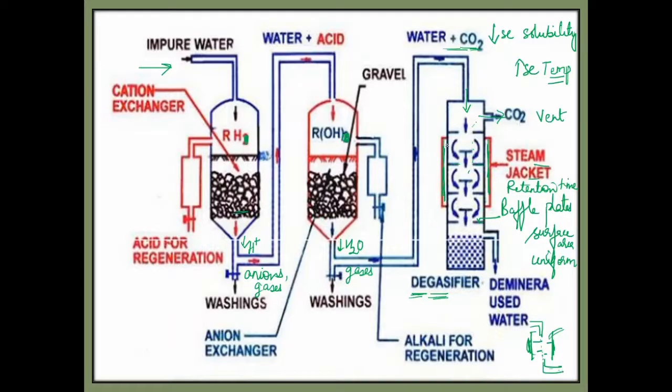What we are doing, we are allowing the water to come here and it will come down slowly. It will move like this, then move like this, and then it will come up. So it is going to spend some time inside. So the time is increased. At the same time, plates are there, so surface area is increased, and it is obviously giving you uniform heating. So the molecule is properly getting heated here, and that is how it helps in removing the gas properly.